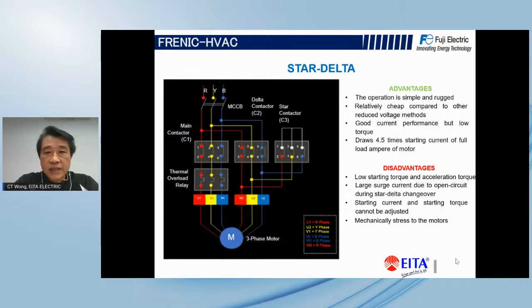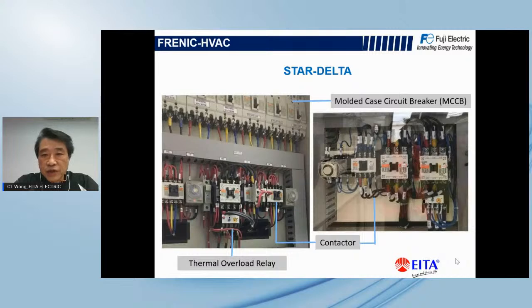The advantage is that, apart from the additional 2 contactors, it is simple and relatively cheap compared with the other reduced voltage starting methods. It will also draw 4.5 times and above of the full load current of the motor. The disadvantage of star delta is that the starting torque is low when you accelerate, and there is a large surge current when you open the star circuit and cut in the delta contactors. This will be the actual picture. You can see 3 contactors on your right hand side, followed by the timers.